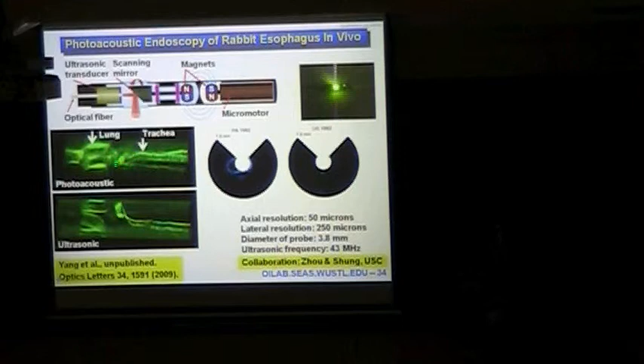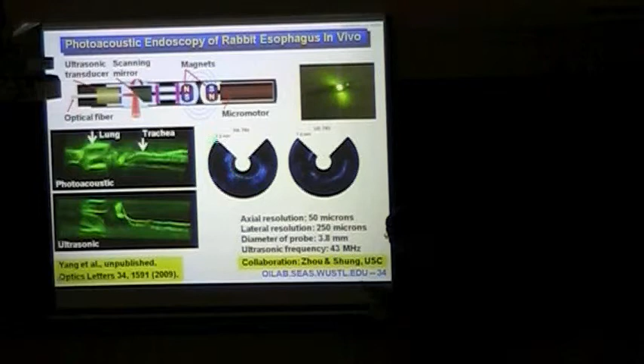An important feature here is that we can penetrate 7 millimeters in the current setup into the GI tract. If you use standard optical endoscopy, your penetration is limited to about 1 millimeter. In many cases, there are deeper lesions. The GI specialists want to penetrate about 3 millimeters or so to capture all the other deeply seated lesions. And this device is the right target device.